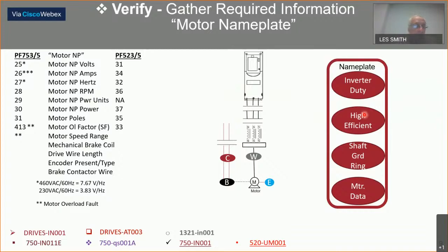Whereas if we take a look here, the 3 asterisks up there, motor nameplate, that's just used for tuning. So if you put the motor nameplate in there and do a static tune, the drive will actually throw out that much current DC wise, because it's not rotational, and we'll do an Ohm's law calibration out there. That's all that's used for. So understand these different parameters mean different things to getting your production drive up and running and keeping it running.